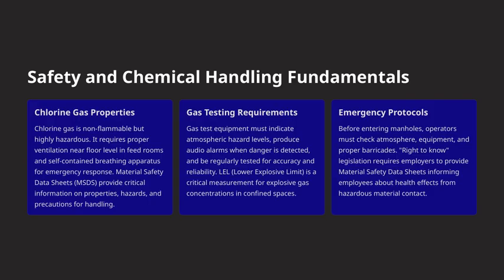Now, moving on to gas testing requirements. It's crucial that our gas test equipment can accurately detect hazardous atmospheric levels. The equipment should also produce audible alarms to alert us immediately if danger is present. Regular testing of this equipment is necessary to ensure it remains accurate and reliable. One of the most important measurements we look at is the LEL, or lower explosive limit. Monitoring this is vital, especially in confined spaces, because it helps us identify if explosive concentrations are approaching dangerous levels.